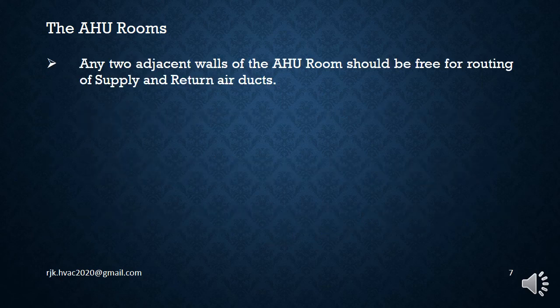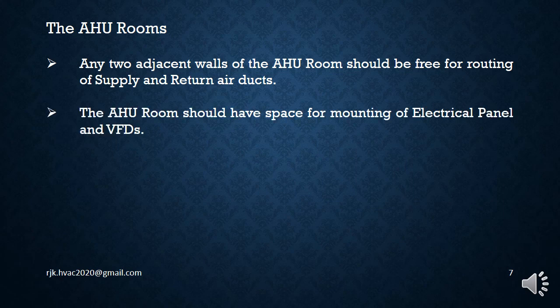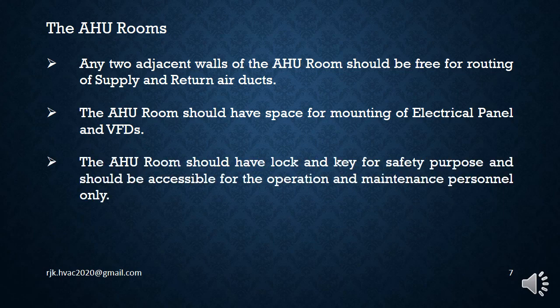Any two adjacent walls of the AHU room should be free for routing of supply and return ducts. The AHU room should have space for mounting of electrical panel and VFDs. The AHU room should have lock and key for safety purpose and should be accessible for the operation and maintenance personnel only.